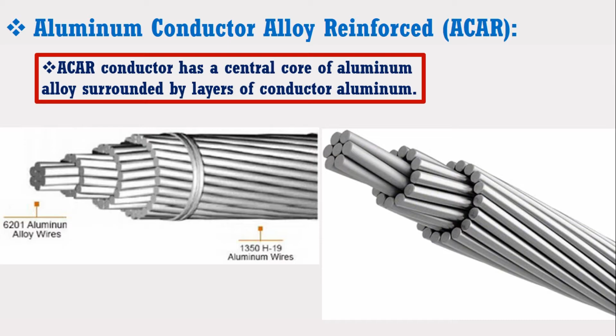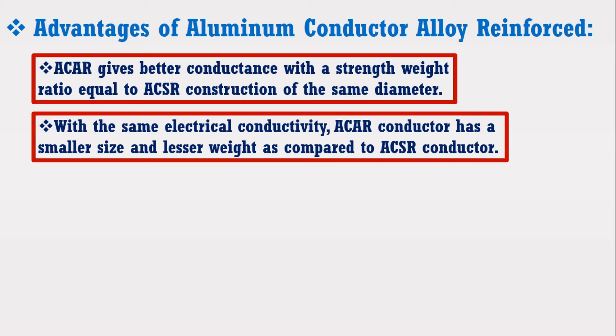Now I am going to discuss about the aluminium conductor alloy reinforced. The aluminium conductor alloy reinforced has a central core of aluminium alloy surrounded by layers of conductors aluminium as shown in the figure. Aluminium conductor alloy reinforced gives better conductance with a strength-weight ratio equal to ACSR construction of the same diameter. With the same electrical conductivity, aluminium conductor alloy reinforced has a smaller size and lesser weight as compared to ACSR conductor. These conductors are widely used in overhead transmission and distribution lines.